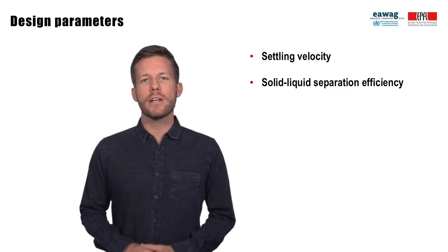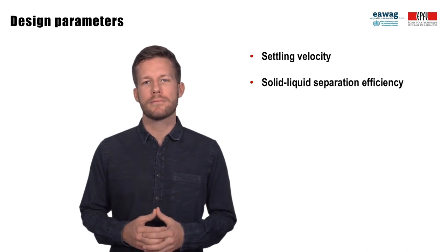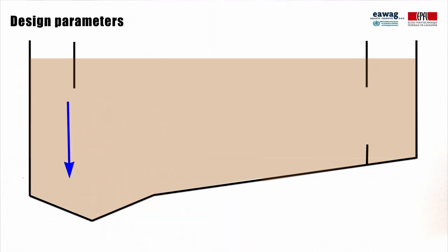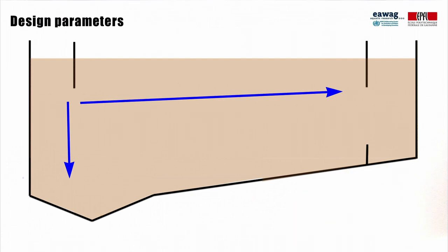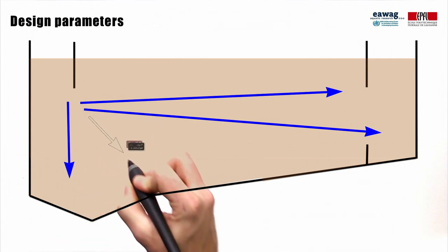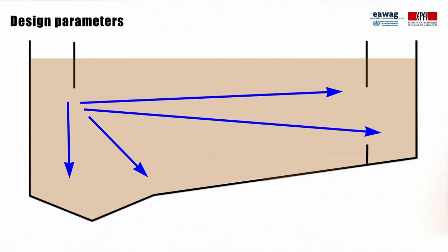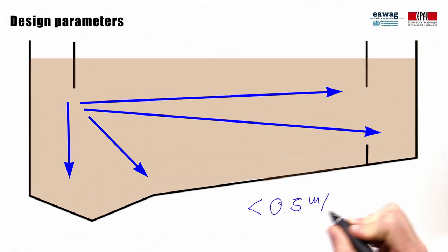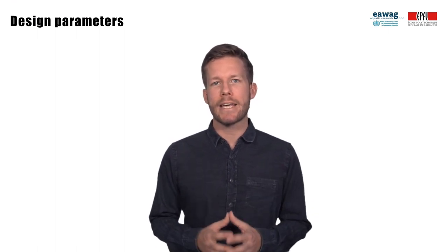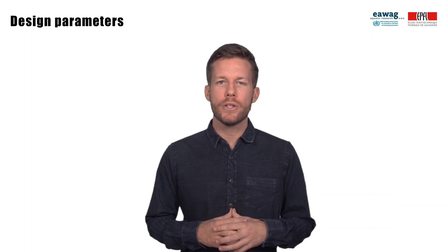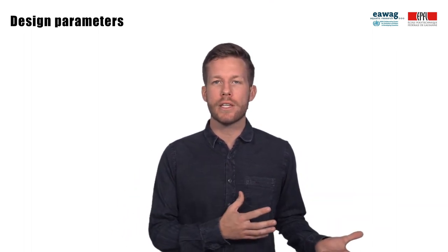The settling velocity and the solid-liquid separation efficiency are design parameters specific to settling thickening tanks. The settling velocity is an estimate of the speed at which solids settle to the bottom of a settling thickening tank. If the speed with which the solids travel through the tank is faster than the settling velocity, the sludge will leave the tank with the effluent. If the settling velocity is faster than the velocity with which solids travel through the tank, the solids will settle out at the bottom. Based on experience from Accra, Kampala, and Dakar, a settling velocity of equal to or smaller than 0.5 meters per hour seems appropriate for fecal sludge in settling thickening tanks. However, experience is lacking on appropriate design values for settling velocity of fecal sludge due to the wide range of fecal sludge characteristics from different on-site sanitation technologies or cities.